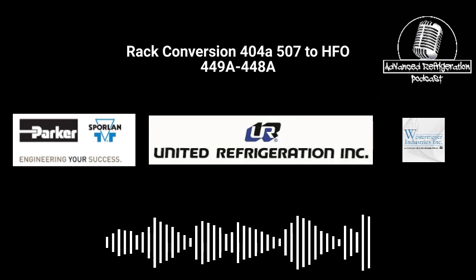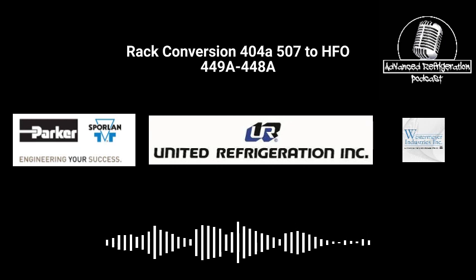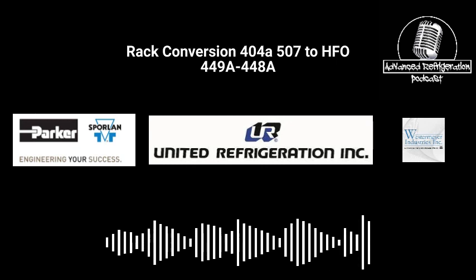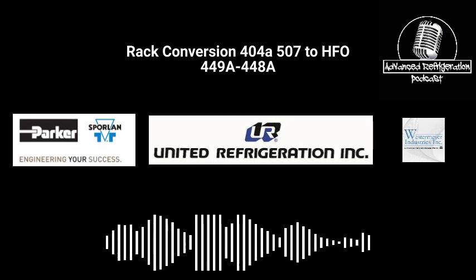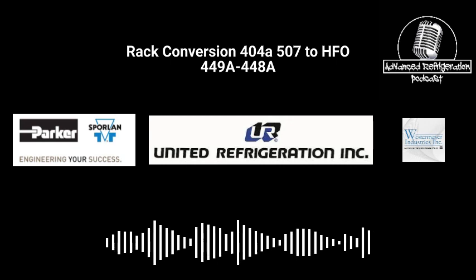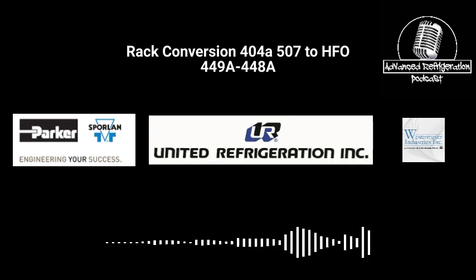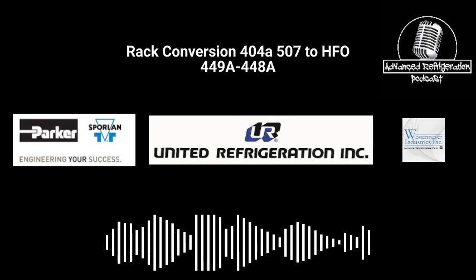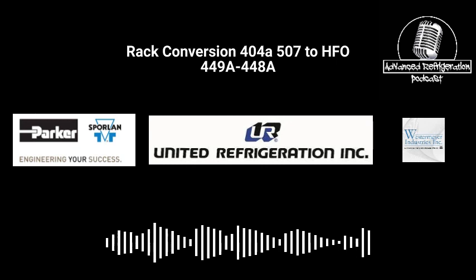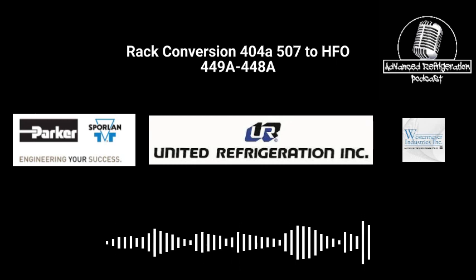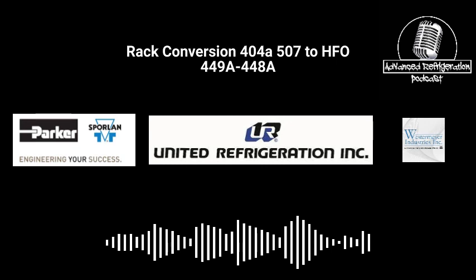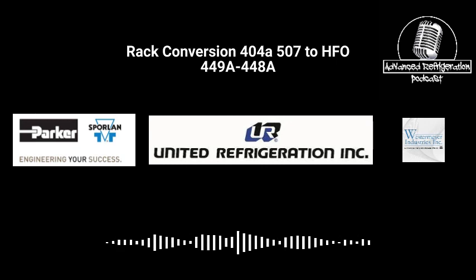When you're talking about the Y1037 valves, or even if you have a temperature sensor on the discharge line basically checking your discharge temperature, if you do not have that sensor wrapped, you will think that you have a bad 1037 valve, because I've done it, and I never did it again. I installed these valves at a store. We were ripping out the scrolls, Copelands, and putting in Bitzers because that's just what the customer wanted. I sized these valves up, and I was like, what did I do? Did I mess it up? I did not read all of the directions. I read most of them, and it says wrap the sensor. And I'm like, no, there's no way that head cooling fan is moving that much air away. Yeah, bullshit. Oh, yeah. No, it did. That bit me in the ass one time too.